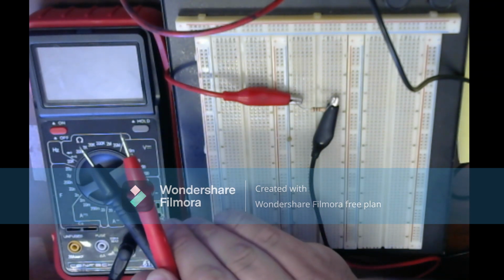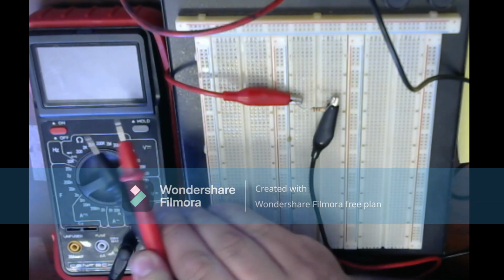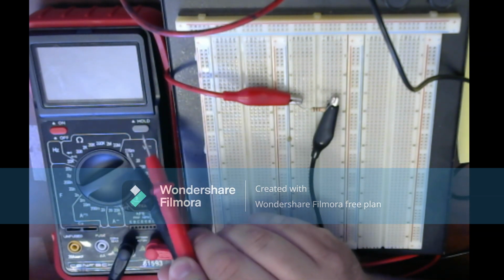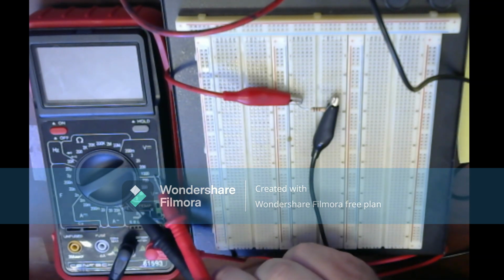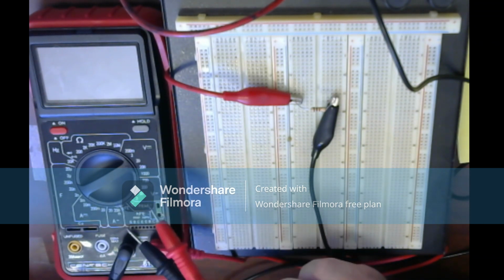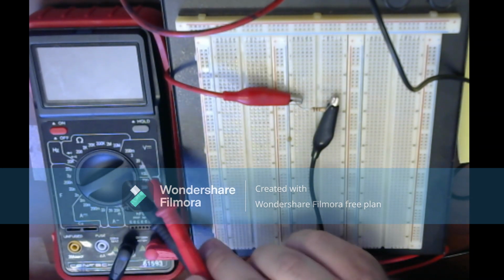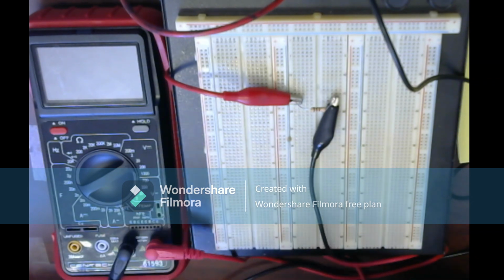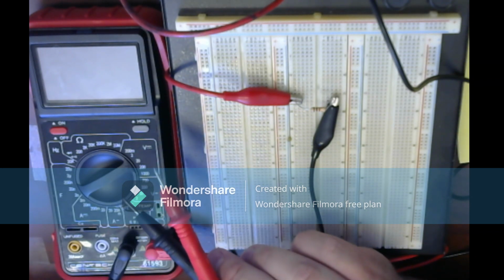Now, one thing you may have noticed is that my DMM has shut off. I didn't push any buttons, the image on the screen just disappeared, and I was holding that voltage. What's going on is this DMM has gone into a power save mode. If it doesn't get used for a while, or sits idle, especially while trying to actively measure, if it doesn't get a signal for a while it will just turn off, and then we have to do some steps to fix that.